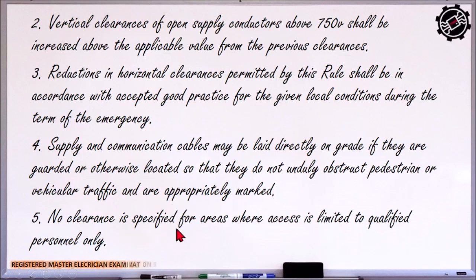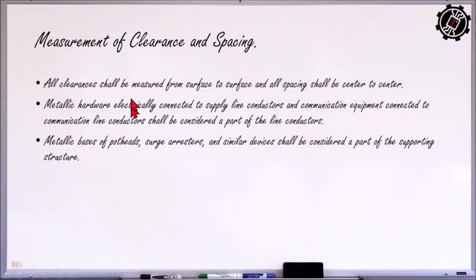So no clearance is specified for areas where access is limited to qualified personnel only. So if a certain area, kunyari nasa loob ng isang substation, tapos may mga overhead na mga wires doon, so there is no clearance, no, specified dito sa rule na to, as long as the access to that location is limited only to qualified personnel. So measurement of clearance and spacing. So paano natin i-measure yung clearance, paano i-measure yung spacing.